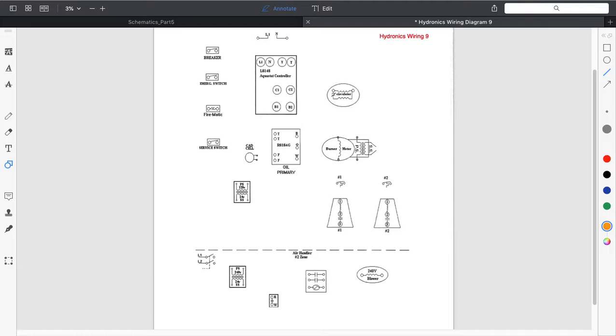Okay, so let's talk about how this is going to work. The first thing we really are going to need to do is let's go ahead and get the circulator circuit out of the way. So I'm going to tie circulator into C1 and C2. And I'm going to try to not cross too many wires here because it becomes a real pain when we're doing this digitally. Now B1 and B2 is going to be what powers the oil primary control. Okay, so B1 is my line voltage going to my oil primary. And that's my B wire.